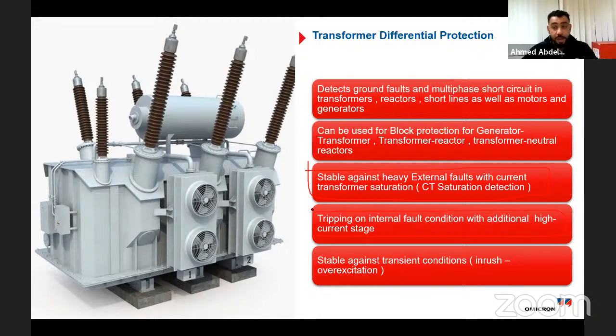So the main requirement of any protection system is that it should be selective, tripping on internal faults, and secure, not tripping in case of external faults, and stable against transient conditions like inrush and overexcitation. This is the main characteristic, or overview, of what the differential protection should do to say that I have a good differential protection. Now, let us see what the challenges in the differential protection system are in the case of a transformer, and we will see how we will overcome them.